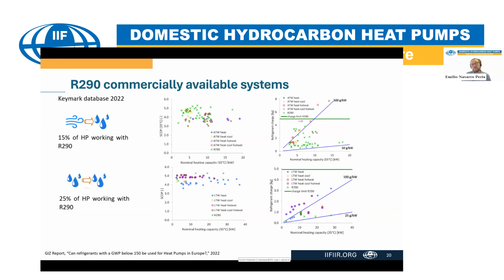Related to that, it's also interesting to make a comment about the figure that I put here on the right side, in which I have represented the refrigerant charge as a function of the nominal capacity for those propane heat pumps. And you can see that for air-to-water heat pumps, you can obtain those values of COP with a specific charge of a little bit more than 50 grams per kilowatt. And if you go to water-to-water heat pumps, these COPs can be obtained with heat pumps that have an even lower specific charge of 25 grams per kilowatt. And this is something that nowadays is commercially available and is supplied in the catalogs of the heat pumps.